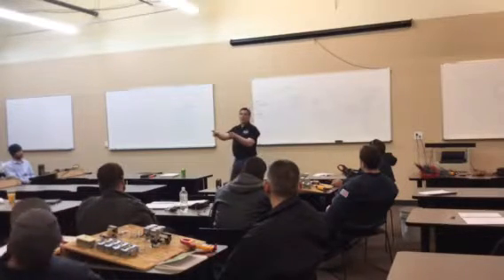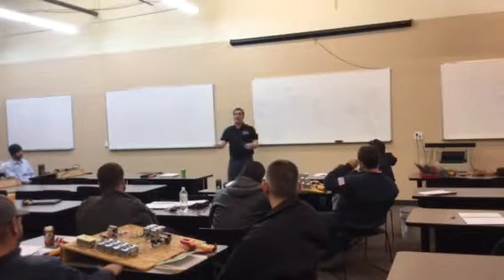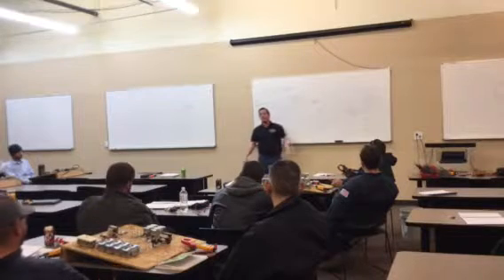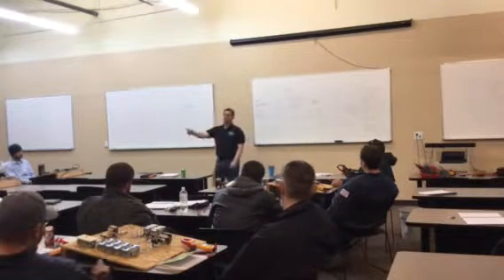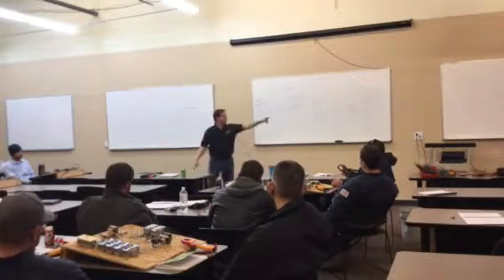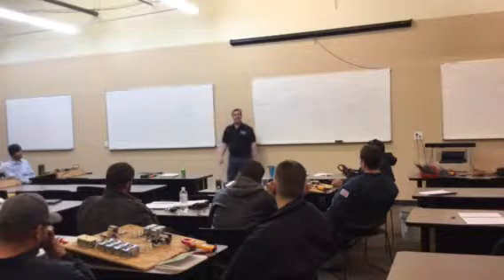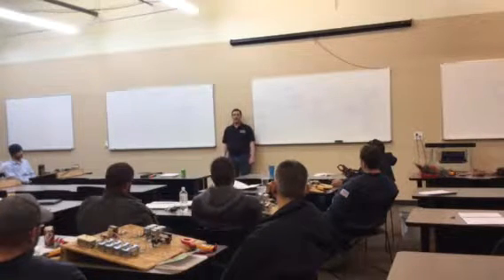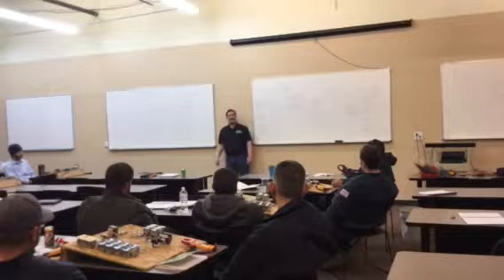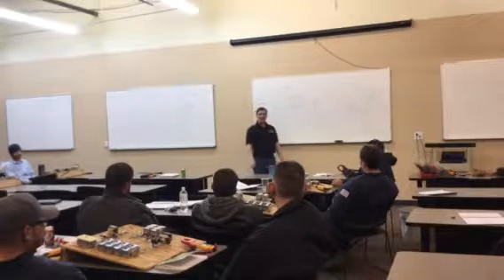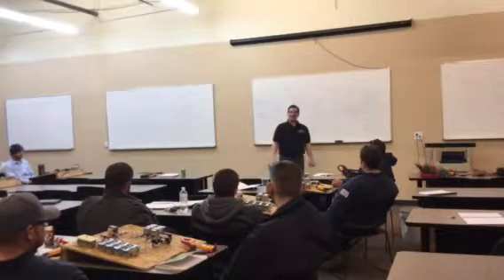When there's no load connected, nothing running, the transformer puts out normal voltage. As soon as something turns on, that voltage will drop to 19 or 10 or some ridiculously low number. What the heck? You're nodding your head. Have you seen something like that happen? Drives you nuts, doesn't it?